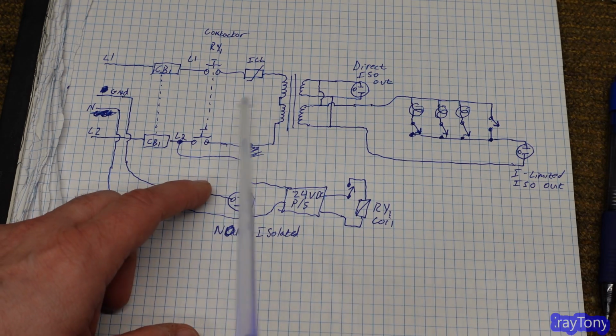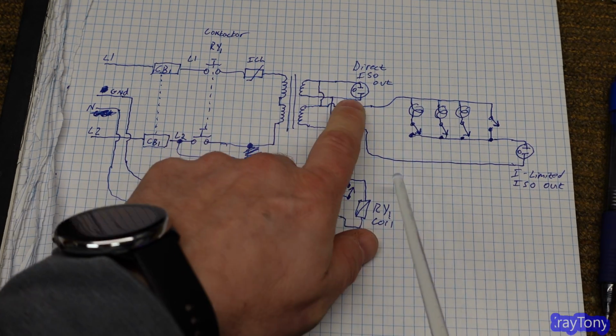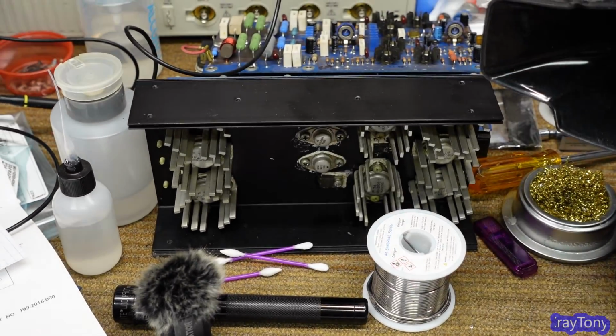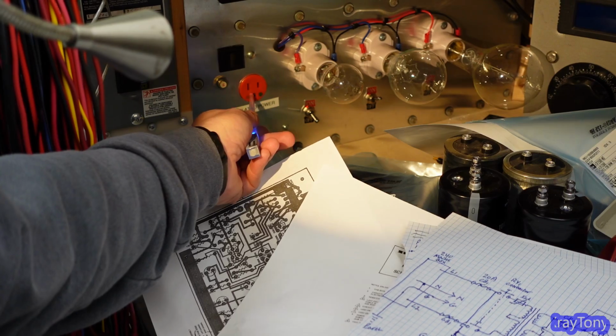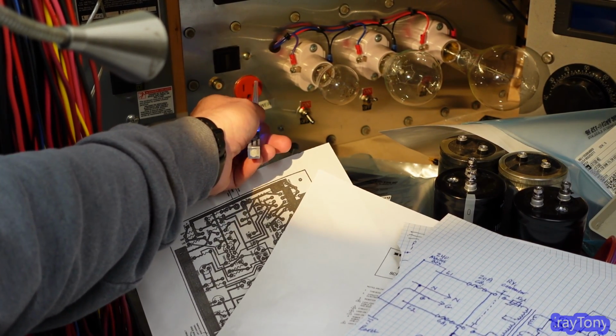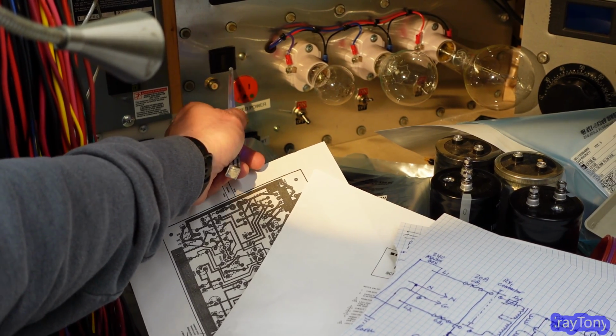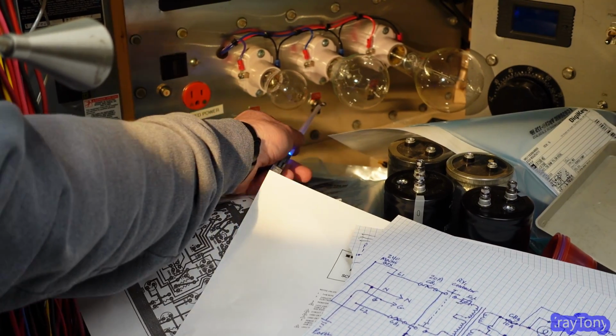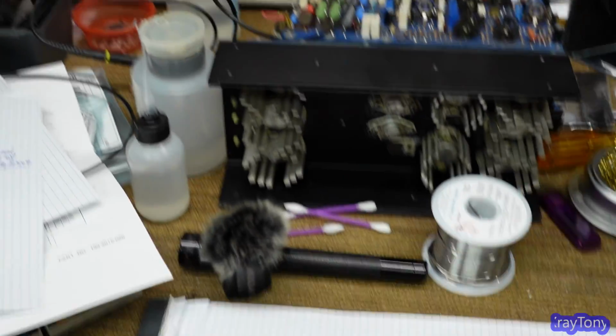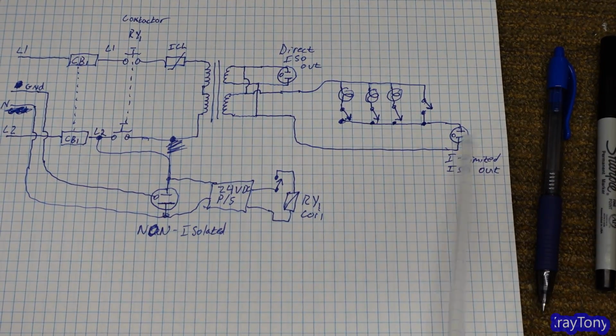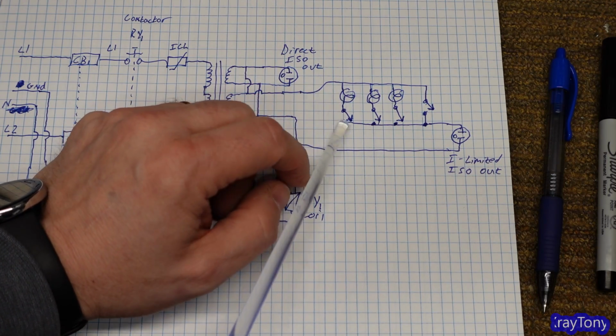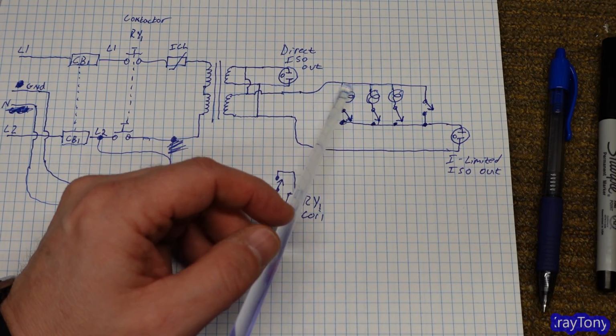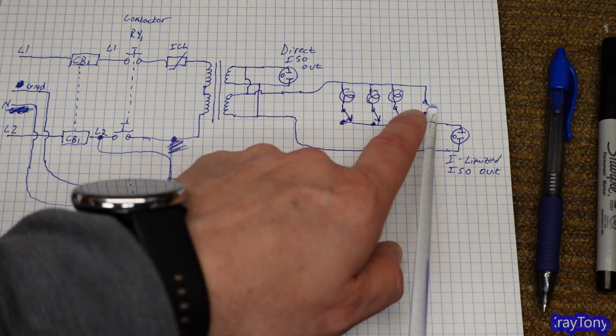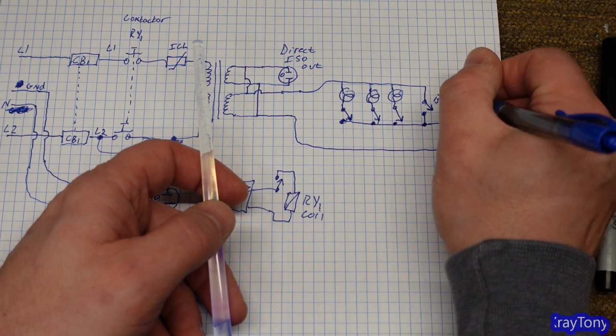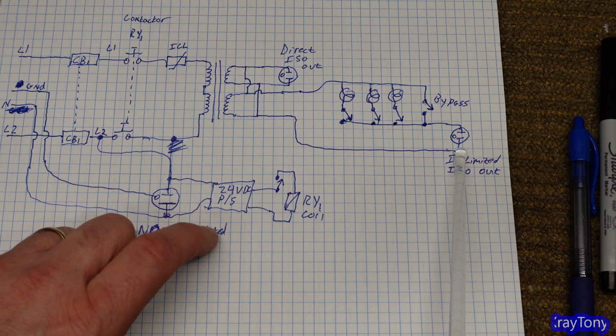Now when I turn this on, I have two different outlets. One is just direct 120 volts, and that goes to this power strip down here, you can see it. The other goes to this outlet right here, and you can see it's orange, so none of the tabs are tied to this prong. It has its own little 10 amp breaker, a switch to turn it on, a bypass, and then there are 3 switches for the current limiting bulbs—that's going to be the current limited isolated output, which is this one right here. So I have 3 bulbs, each going from one leg of the output through a bulb and through a switch. So if I turn all 3 switches off, and turn the bypass switch off, there will be no power going to this outlet.